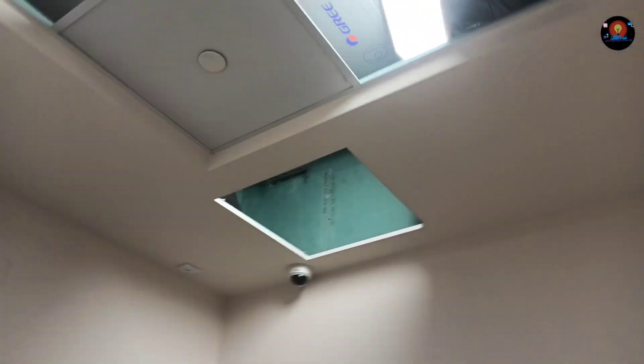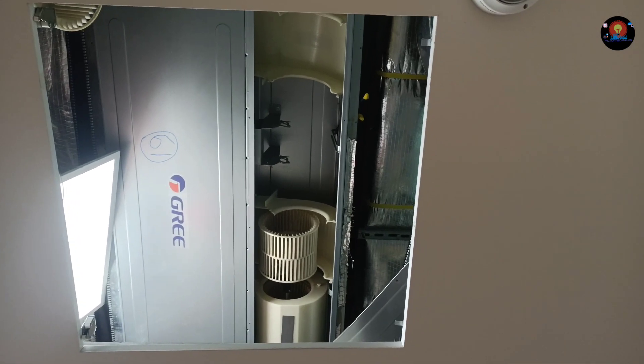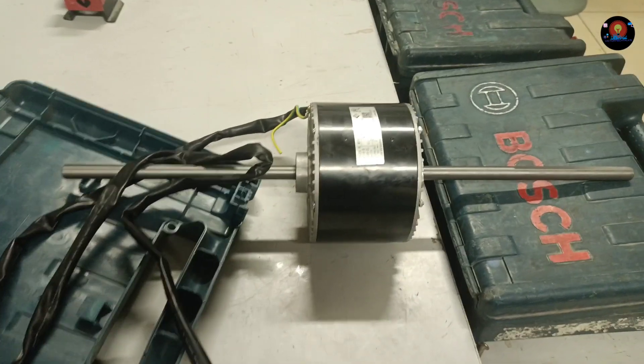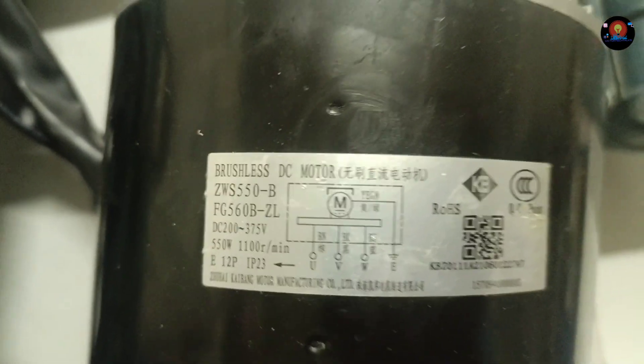This is our new motor, and I will show you in this video. In the previous video we opened this motor and saw there was no good motor inside. This old one is already in our workshop. Basically this motor problem is caused by a heating problem, and that is what gives the L1 error. L1 is the protection of this motor.